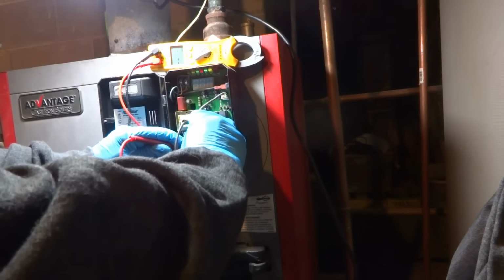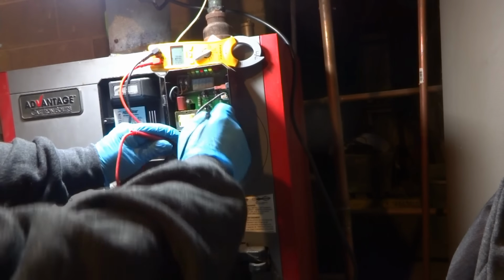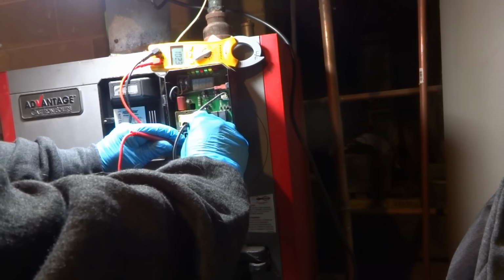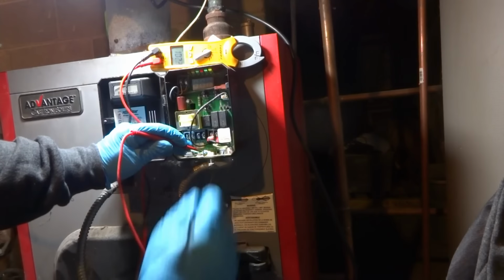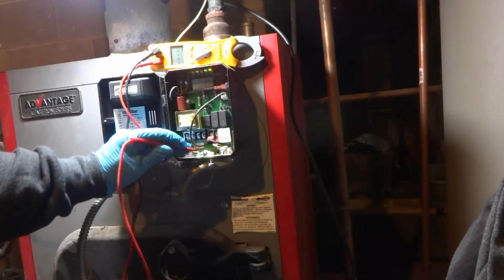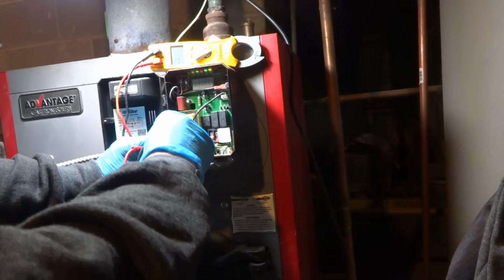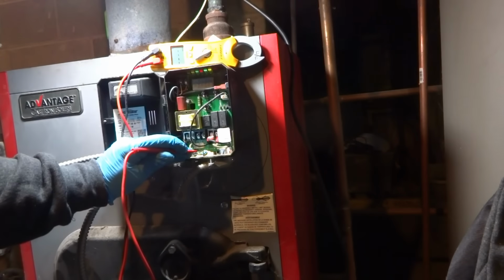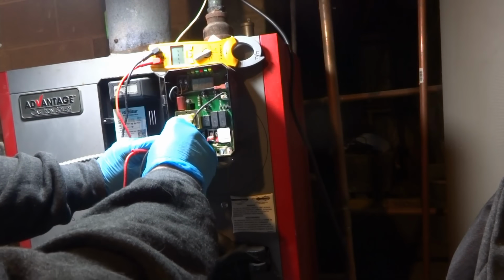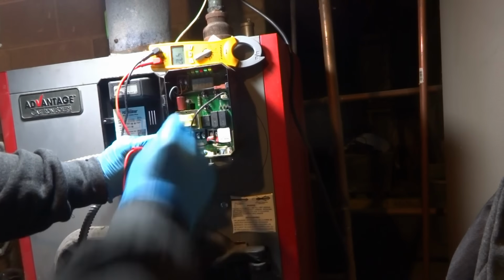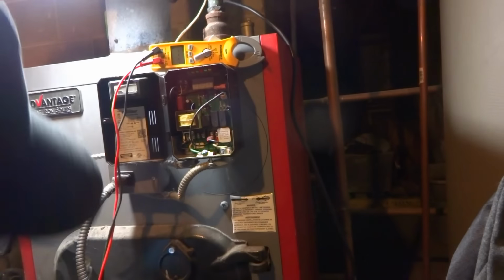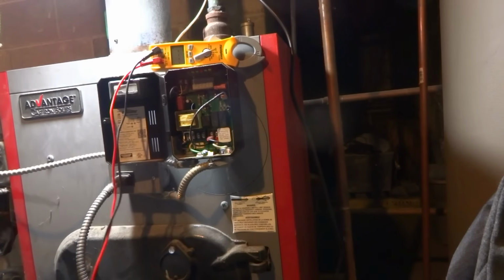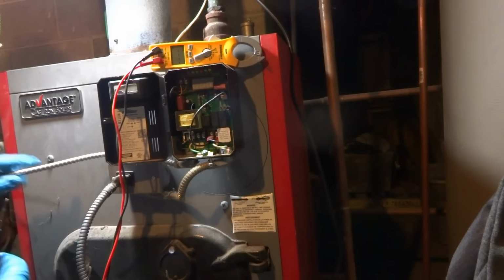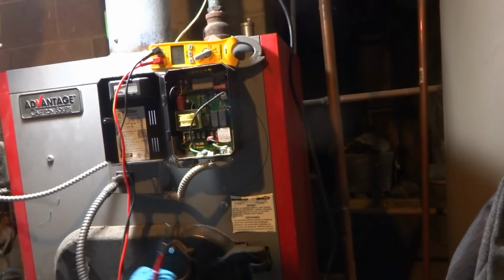That's the burner, so that's not making any noise, but it's showing something. And there's L1, L2 coming in here. There's our problem right there, our main line coming in is shorted. Hear it? Okay, that's the main line coming in from the breaker panel, from here, from there. You see that? Yep, so that's an electrical issue.